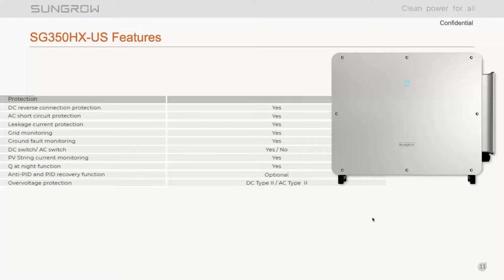PV string current monitoring. The Modbus map with the inverter has the capability of monitoring string currents and voltages at an input level, so DC1 and DC2 for each MPPT, both positive and negative, or you can just monitor on an MPPT level. So depending on what kind of bandwidth you want to use on your monitoring platform and how many registers you want to have your SCADA provider pull, you can still get down into the individual input level to monitor your DC health.